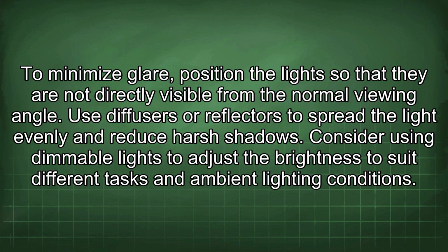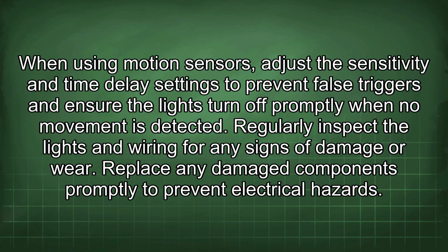Consider using dimmable lights to adjust the brightness to suit different tasks and ambient lighting conditions. When using motion sensors, adjust the sensitivity and time delay settings to prevent false triggers and ensure the lights turn off promptly when no movement is detected. Regularly inspect the lights and wiring for any signs of damage or wear. Replace any damaged components promptly to prevent electrical hazards.